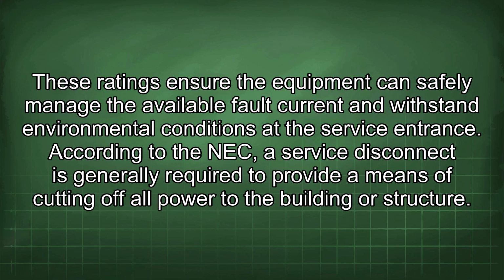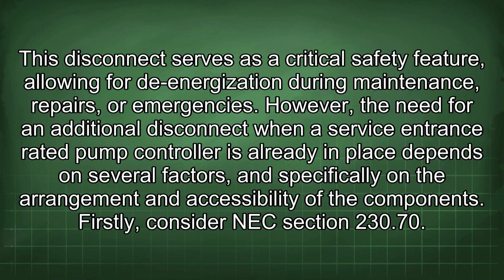entrance. According to the NEC, a service disconnect is generally required to provide a means of cutting off all power to the building or structure. This disconnect serves as a critical safety feature, allowing for de-energization during maintenance, repairs, or emergencies. However, the need for an additional disconnect when a service entrance rated pump controller is already in place depends on several factors, and specifically on the arrangement and accessibility of the components.